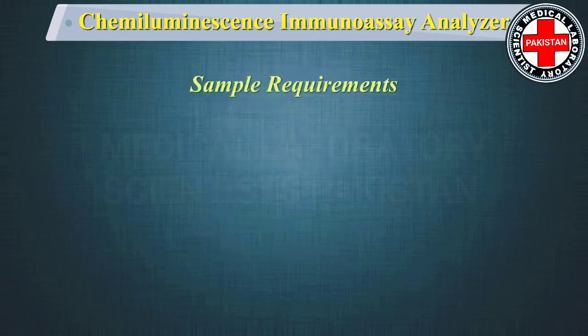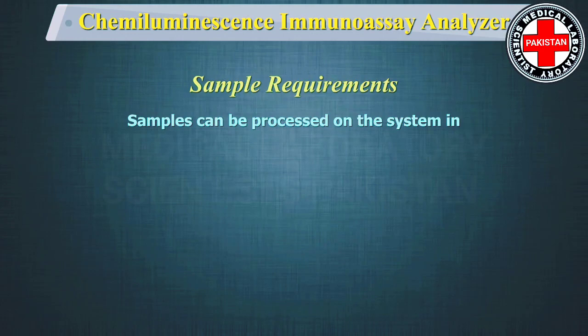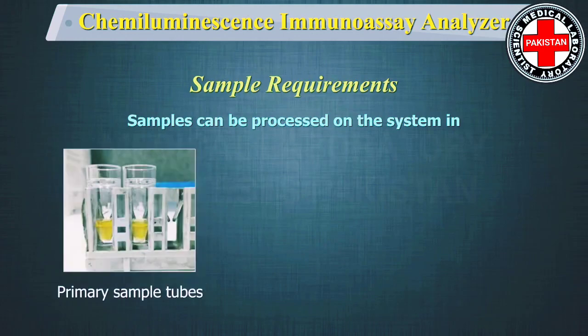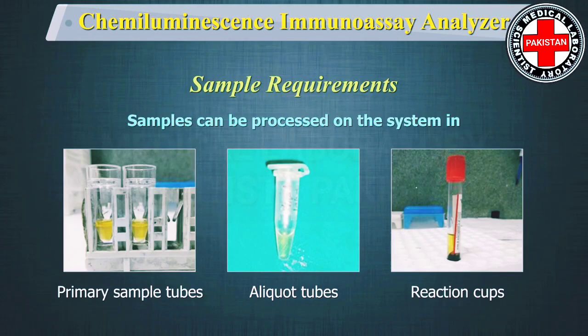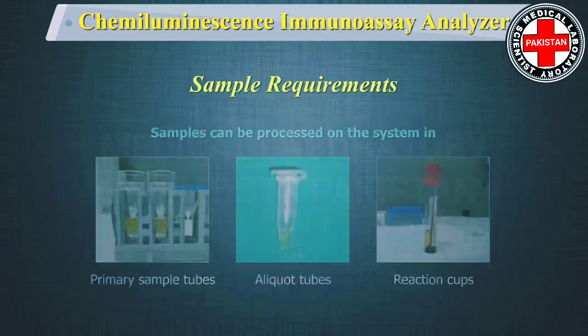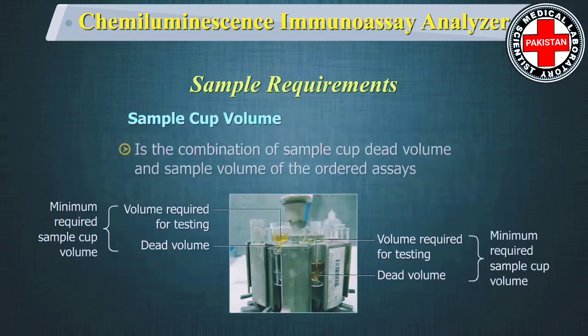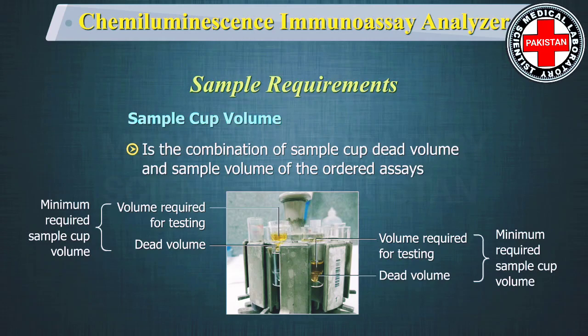Samples can be processed on the system in primary sample tubes, aliquot tubes, or reaction cups. Adequate sample volume is important to get reliable assay results. Sample cup volume is the combination of sample cup dead volume and sample volume of the ordered assays, which is usually specified by the reagent manufacturer on the package insert or reagent application sheet.